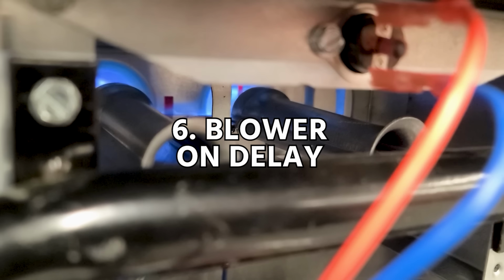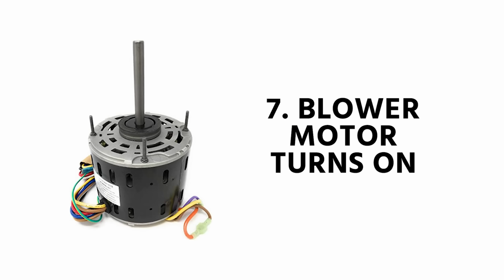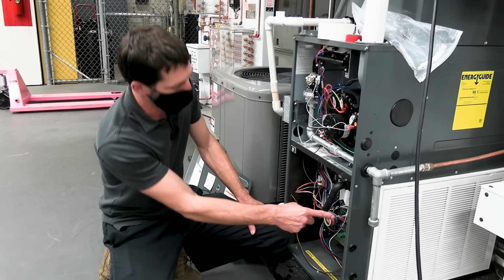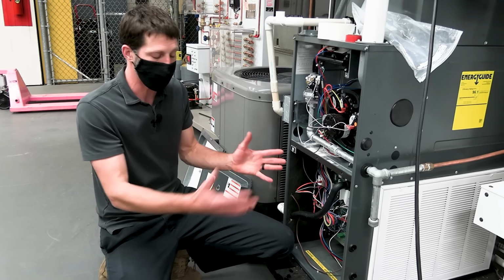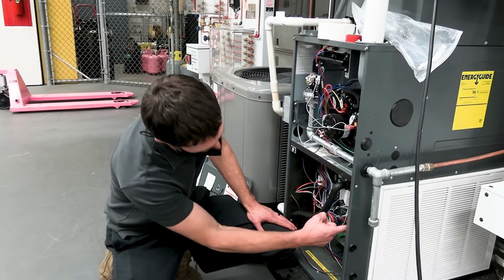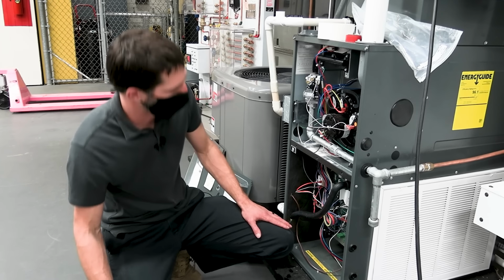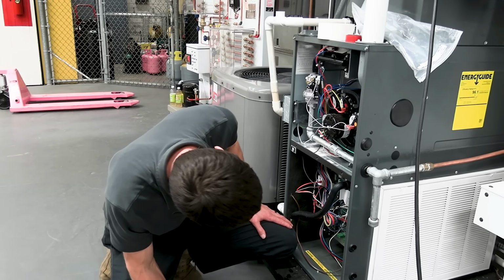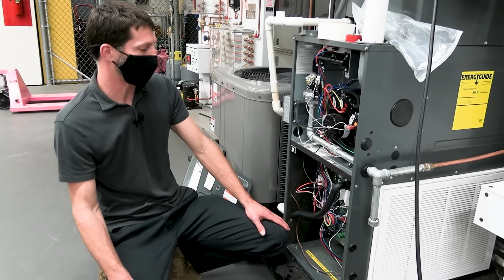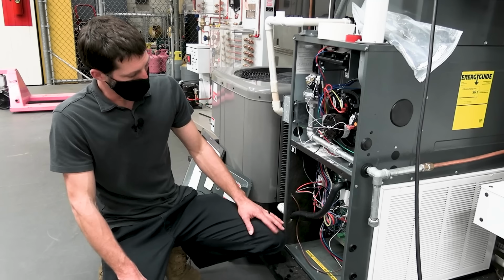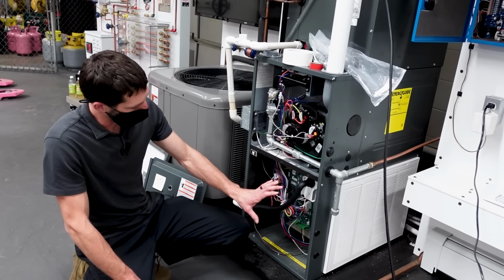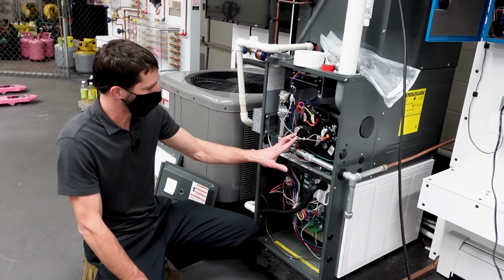So the control board is going to wait for the primary and secondary heat exchangers to heat up, so you're not blowing low temperature air in the building. And then after the blower on delay, the control board turns the blower motor on. Now in this case, you have a variable speed ECM motor. Some of these have a multi-speed ECM motor. This is an ECM variable speed. It looks like a newer version of the 3.0, or it might be a different manufacturer. I'm not sure, the plug looks a little different than what I'm used to seeing. Anyway, this is a variable speed blower motor right here, and this is a PSC inducer motor.